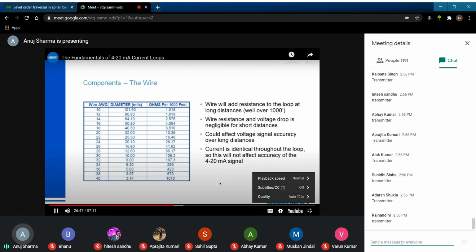The same milliamps put out by the transmitter are the same that arrive at your receiver, regardless of what the wire does to resistance or voltage drop. So in a 4 to 20 system, you really don't need to worry about the wire unless you're running close to that voltage cap, which I generally recommend against anyway.